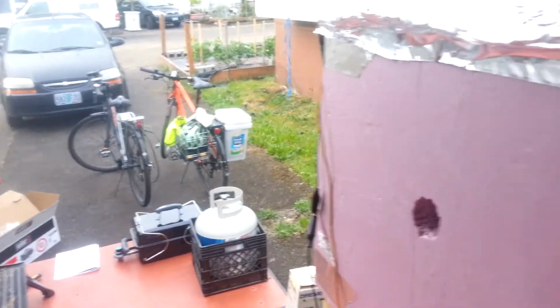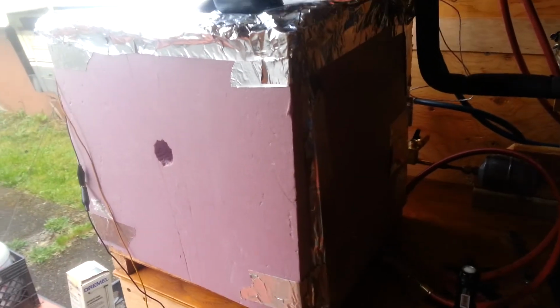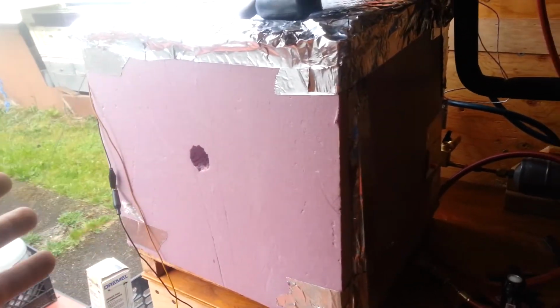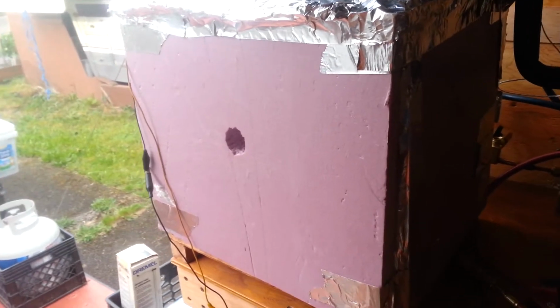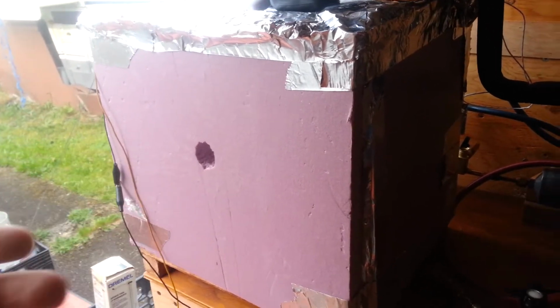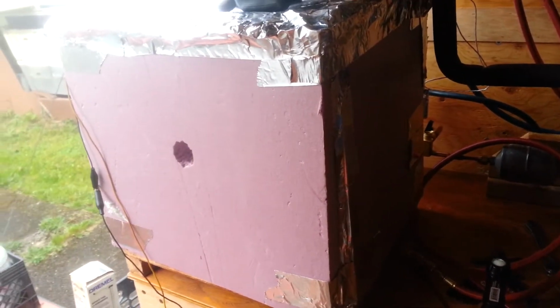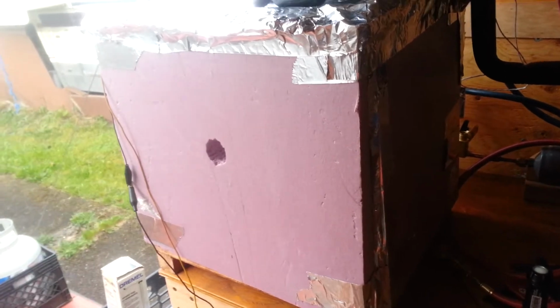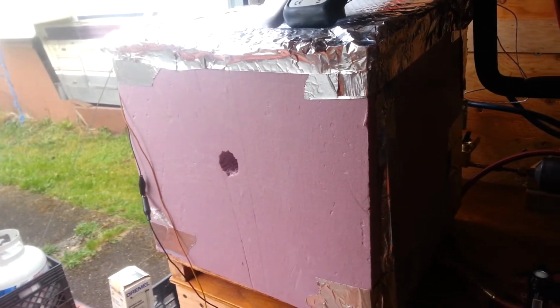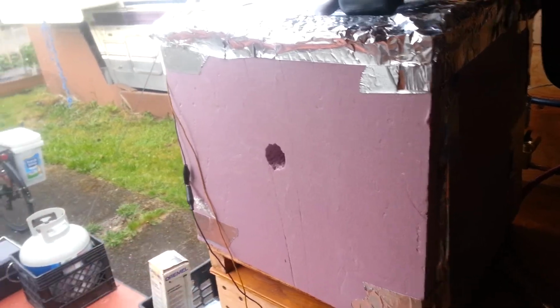the load is maintained. Now, the problem with doing that, and I've found this out, is that, well, this box isn't perfect. I mean, it's not insulated very well. It's 80 degrees outside right now. So, the heat being pulled into the box, the heat being conducted into the box, might overcome the ability of the system to carry it away, and it actually might even get to the point where it just matches at a particular setting on the throttle. What I found myself doing was actually cranking it down a little bit to lower the pressure, increase the delta T, so it carries it away faster.